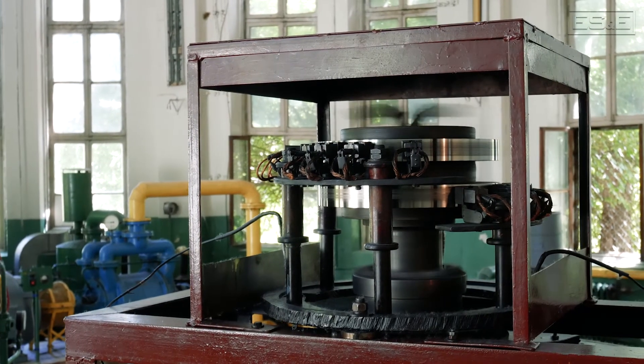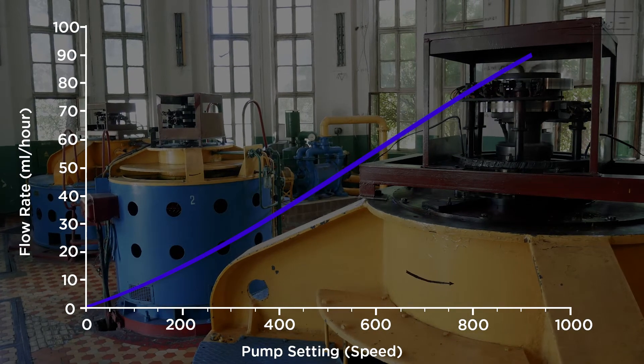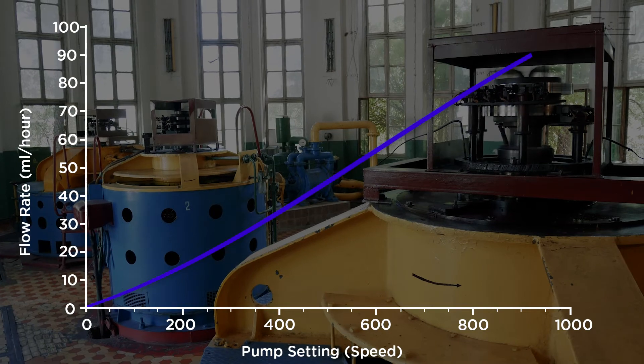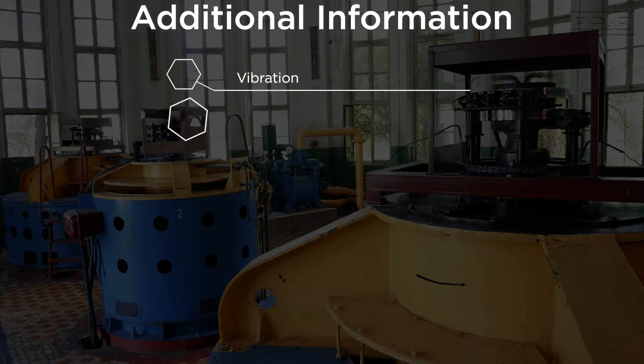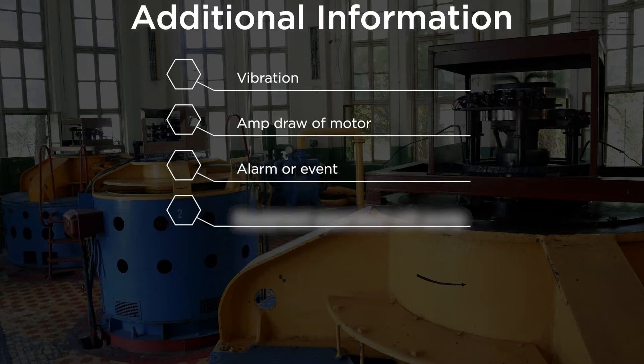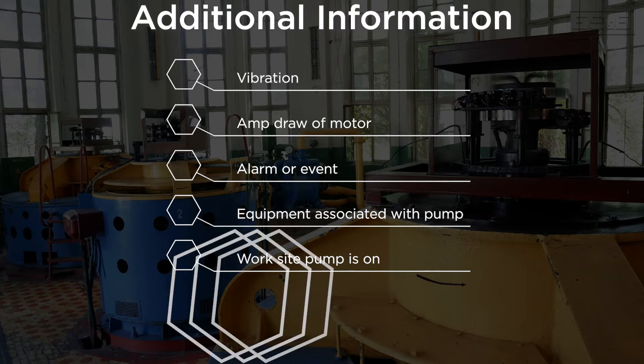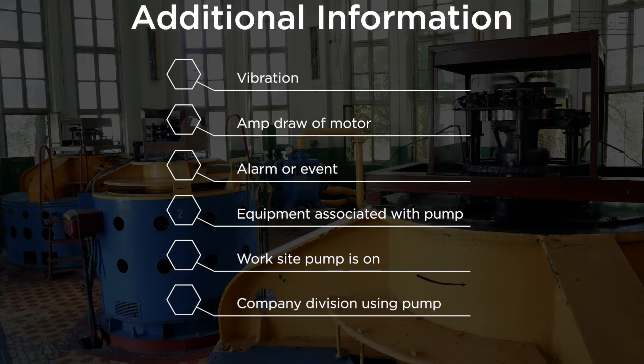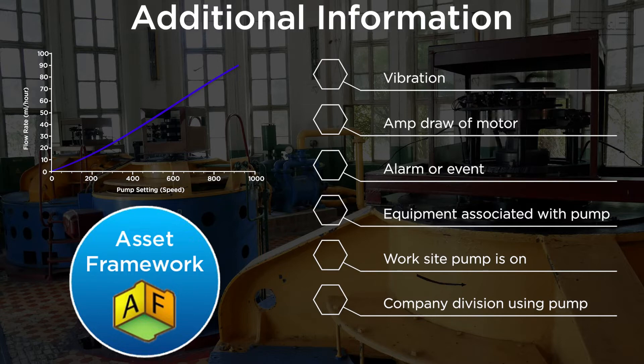Let me give you an example. Say you have a pump. One of the typical values captured when monitoring pumps is the flow rate. However, there's additional information that would be nice to know alongside that flow rate at the time it was captured — for example, vibration or the amp draw of the motor running the pump. Maybe an alarm or event that occurred — we'd like to know when that event happened and at what flow rate. Maybe we'd like to know what piece of equipment that pump is associated with, what site it's on, what division within the corporation. All that information is valuable. With asset framework, you can capture that alongside the flow rate, thereby creating that context or those relationships.